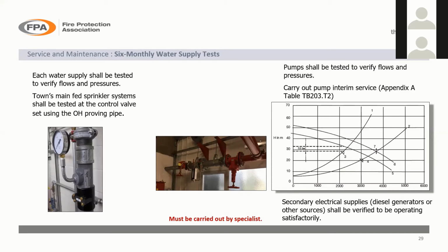And if you do this on a regular basis, as required by the rules, and plot one for each of your pumps, you'll be able to tell whether there's any kind of deterioration in the system over a period of time. Now, obviously, you've got to maintain having the systems serviced on a regular basis, and so you should be able to pick this up, but what you don't want to find is that suddenly your pumps are performing below duty. That applies in any circumstance, but particularly if they're pumps designed for full hydraulic calculation and certain duties that you need to meet, or pre-calculated where you've got a nominal duty on the pump curve. You don't want those pump curves dropping below the curve. You want to try and maintain a little bit above so that the pumps have always got just a little bit in hand.